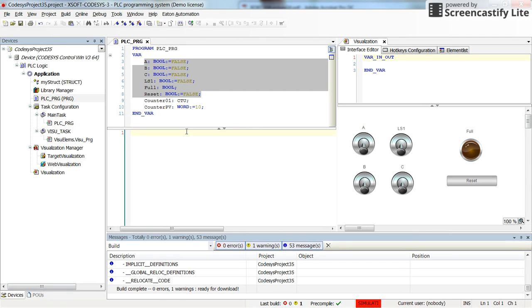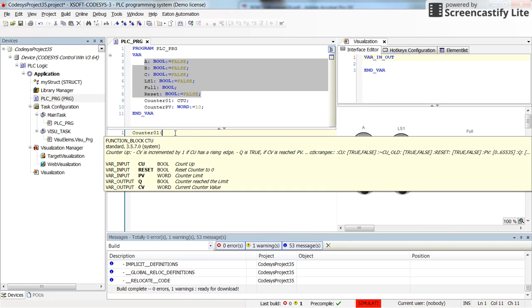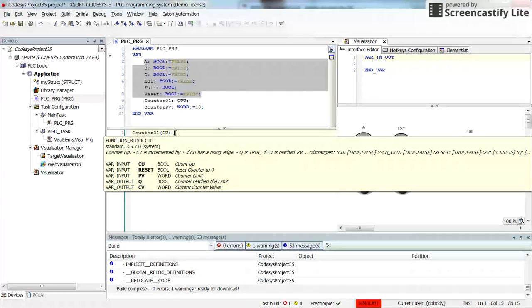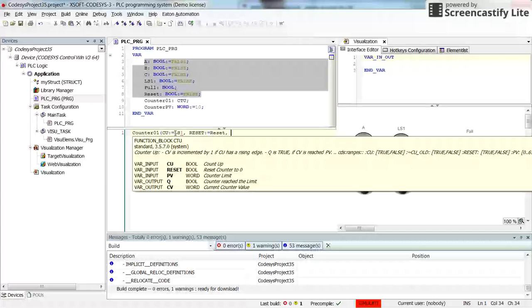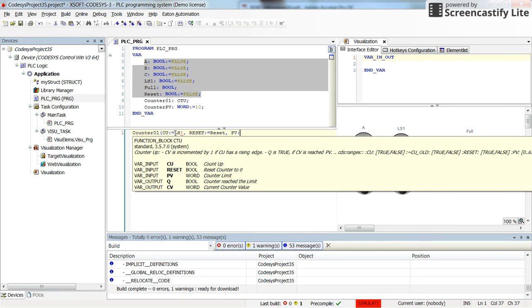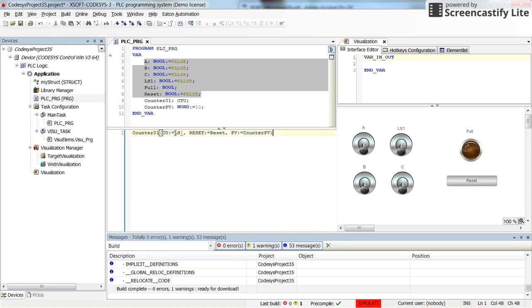To start the program, I'm going to determine the inputs for the counter01. So I will type counter01 then open the parenthesis. The counting up will receive value from the LS1, then reset will be determined by the reset, and the PV will be determined by the counter PV. And that's all for calling the counter.